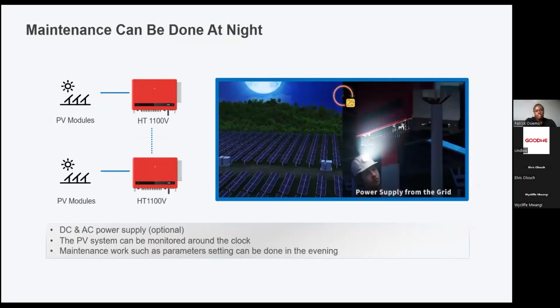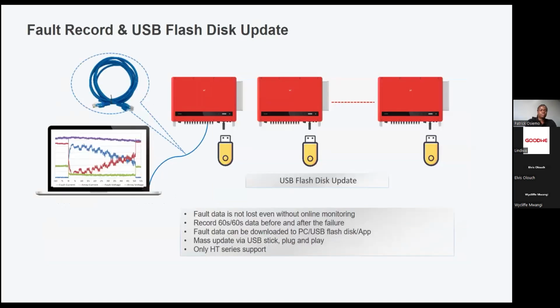We also have maintenance at night with our inverters. The reason is that the inverters can be powered on from either the DC side, the PV that is, or the AC side of the inverters. So in case you want to do your maintenance at night and don't want to interrupt generation happening during the day, you can visit the site, or you can troubleshoot remotely at night and still get the same data, or analyze data downloaded from the portal as well. So maintenance at night is quite a unique feature.